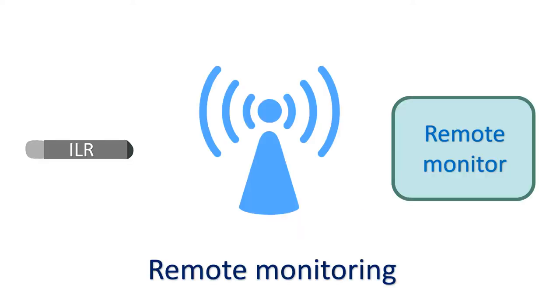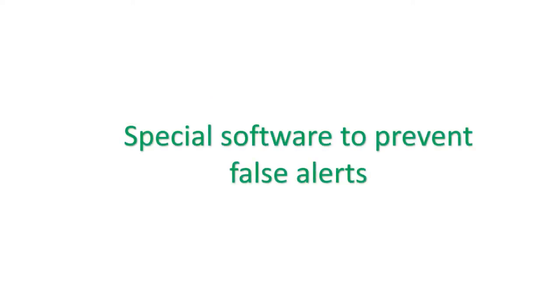Remote monitoring with alert notification allows early detection of significant events. But sometimes the device may also give false alerts, increasing the workload of the monitoring staff. This is now being taken care of by improving the computer program within the device to avoid false alerts. Positioning of the device during implantation is also adjusted to pick up the electrical signals of the heart in the best way. The latest devices with such specialized software to prevent false alerts and extra transmissions claim to have a battery life of up to 4.5 years.